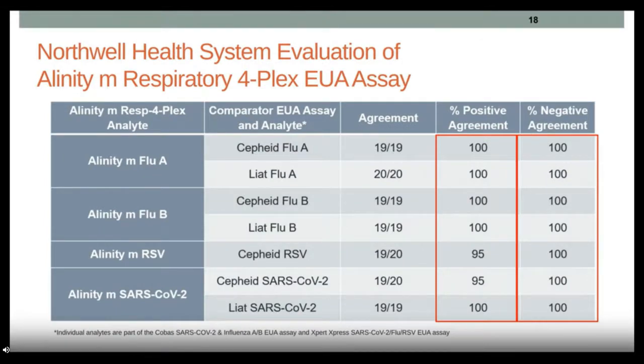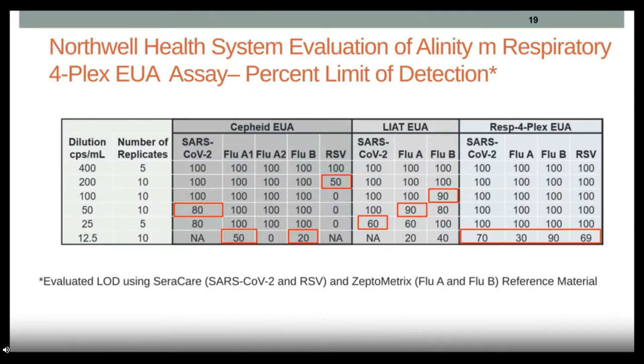Comparing the Alinity M to the Cepheid and Cobas Liat, we found a very high degree of positive percent agreement and 100% negative percent agreement across all analytes. The only notable difference was 95% positive percent agreement for the Cepheid versus Alinity for RSV. One important note: the Liat does not have RSV — it only detects flu A, flu B, and SARS-CoV-2 — which is why only the Cepheid was used as the RSV comparator.